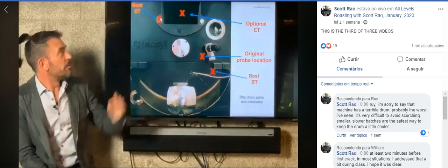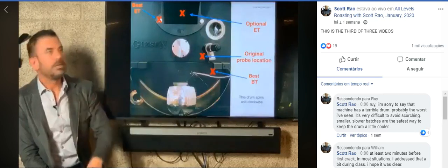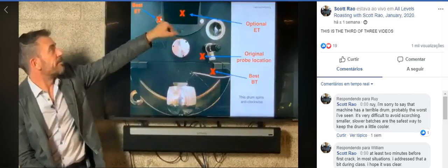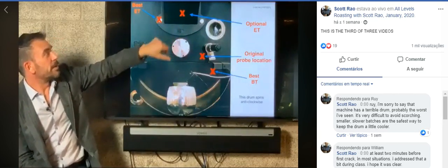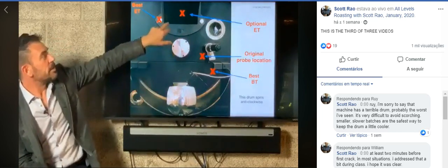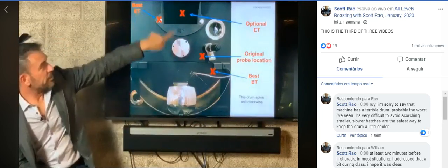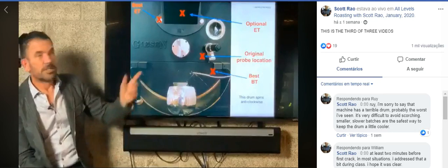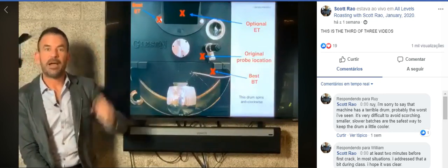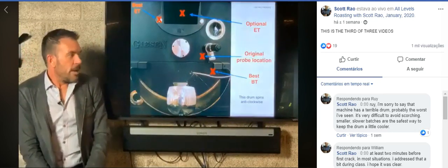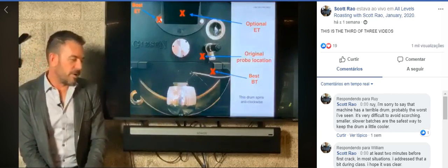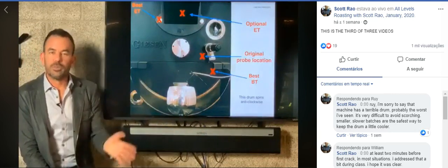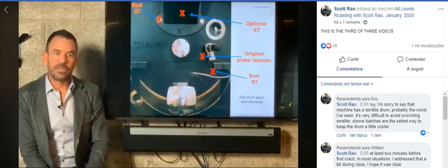The ET probe, we've talked about how they're all over the place. Sometimes they're up in the neck of the loading funnel. Sometimes they're put in place of that bolt on the loading funnel, but usually the one that's opposite from where the bean probe is. Sometimes it's an exhaust probe, meaning it's in the back, close to the fan. All of them are fine. None of them are wrong. Their curves will look slightly different depending on which location you're in, and that's okay.